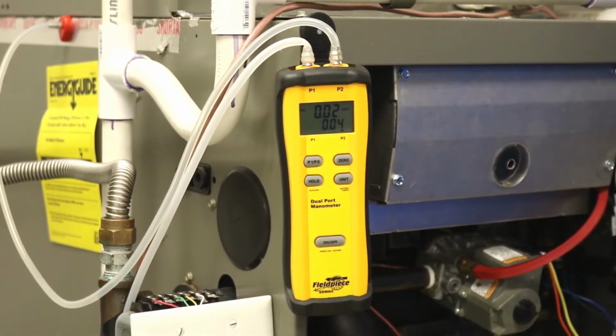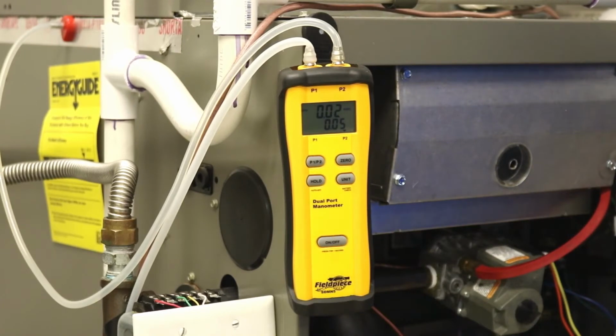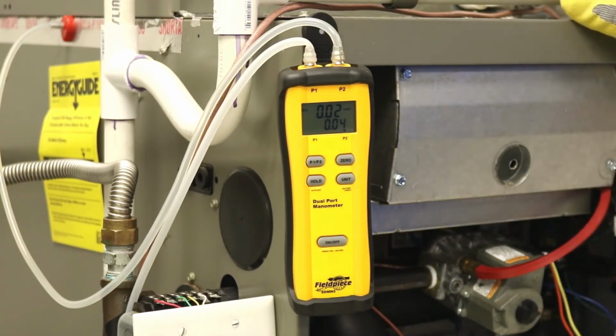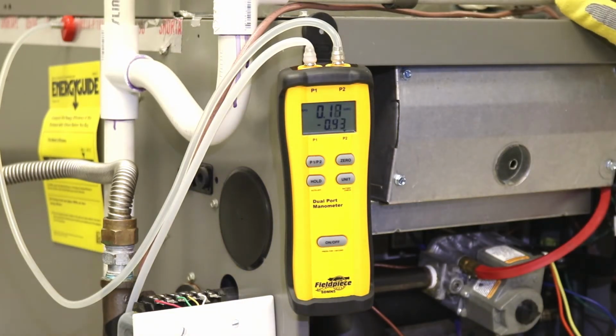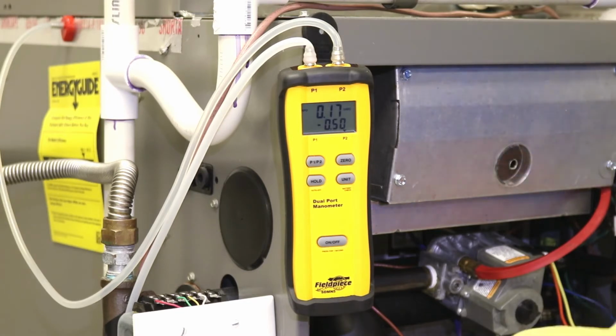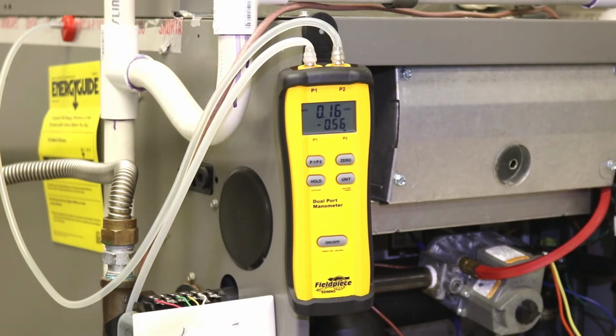So from this point, we're going to turn the system on. We've got our manometer on already. Let's see what she has. Right now, the static pressure of this system, which for our purposes, we're in a lab here and don't have a lot of ductwork running to the system, and it deadheads right above the unit, so it's going to be a little bit off. But for this particular system, and it's not outside of the realm of normal, this particular system is running at a 0.17, 0.16, kind of teetering back and forth between those inches of water column.